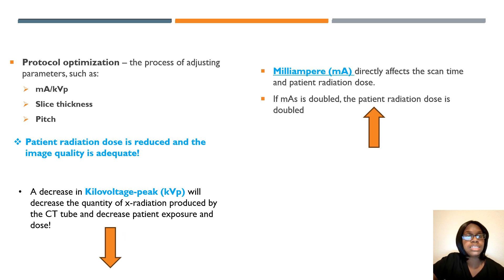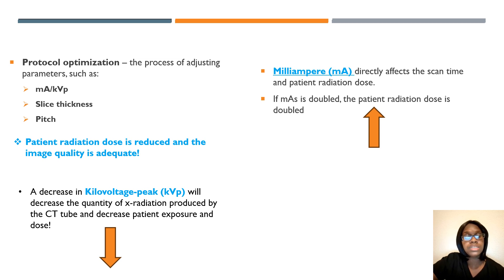Protocol optimization is the process of adjusting parameters such as MA, KVP, slice thickness, and pitch so that patient radiation dose is reduced while image quality remains adequate. A decrease in KVP will decrease the quantity of x-rays produced by the CT tube, decreasing patient exposure and dose. MA affects scan time and patient radiation dose — if MA is doubled, the patient radiation dose is doubled.